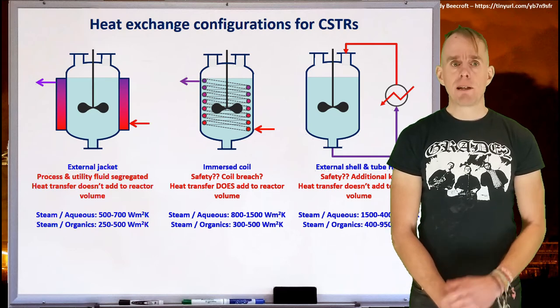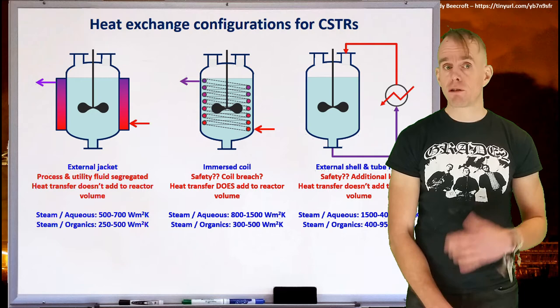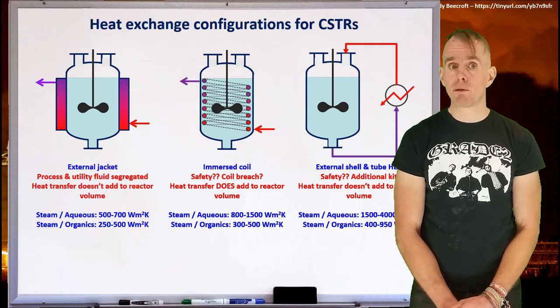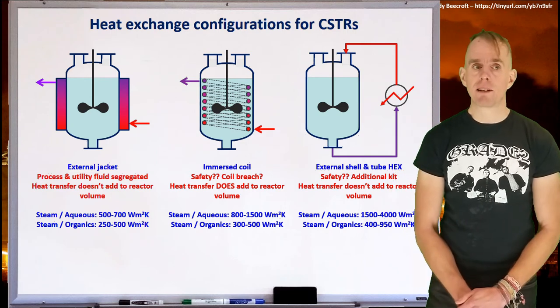If we have a look at those heat transfer coefficients, again, we can see that there may be three times or more compared to an external jacket. So steam on aqueous, 1500 to 4000 Watt per square meter Kelvin, and steam and organics, 400 to 950 Watt per square meter Kelvin.